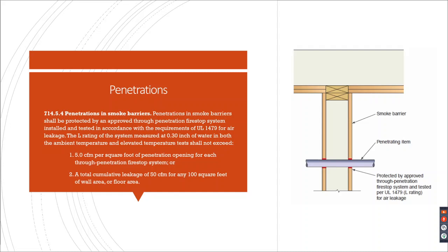Generally, we could see both, of course, but we typically see the one that complies with number 1. Just please don't forget that it's not just the wall. I think they say you have to say it 7 times. Don't forget that this includes the floor sealing assembly and roof sealing assembly when it's part of the smoke compartment, not just the wall.